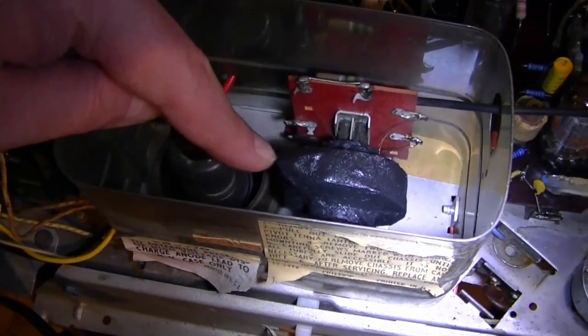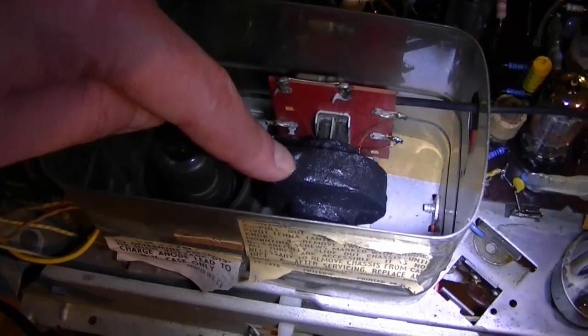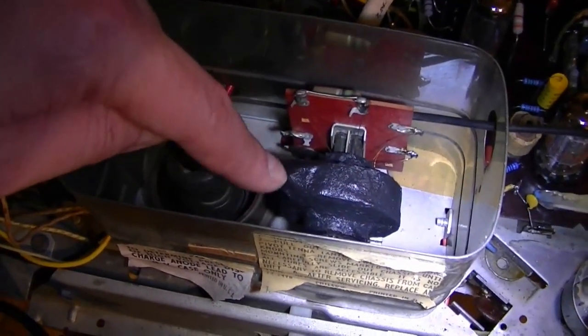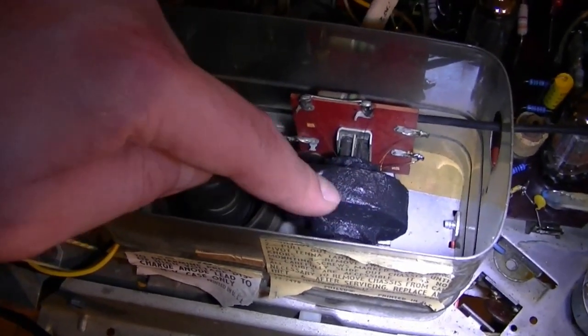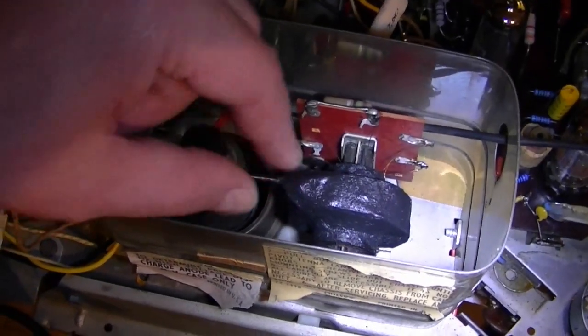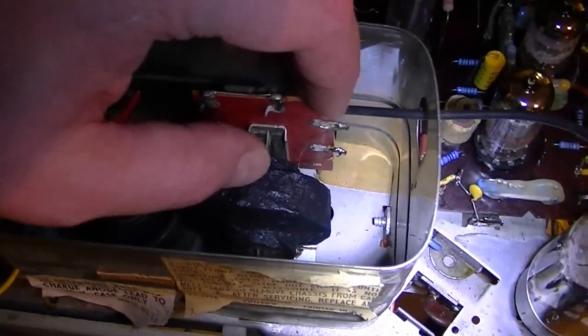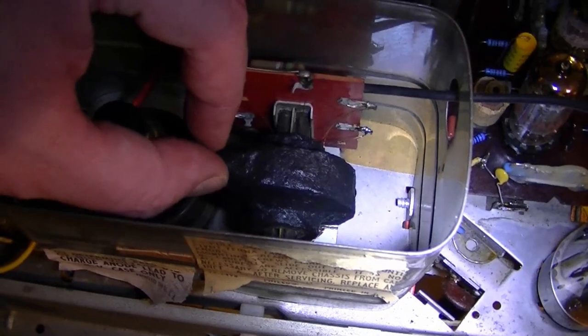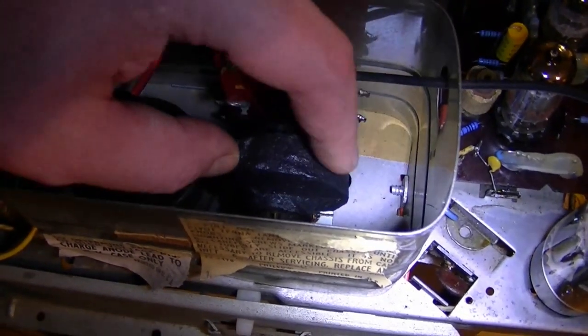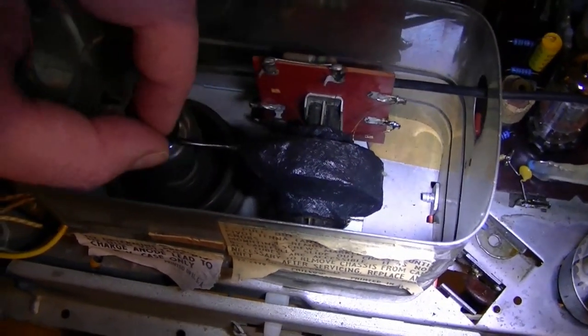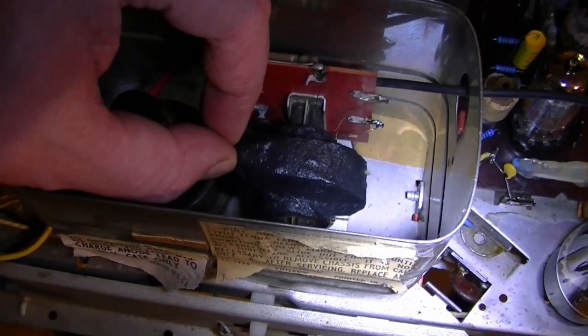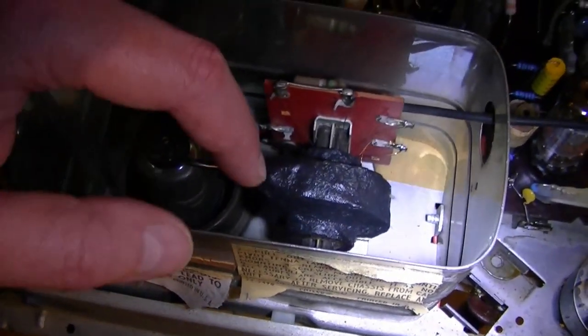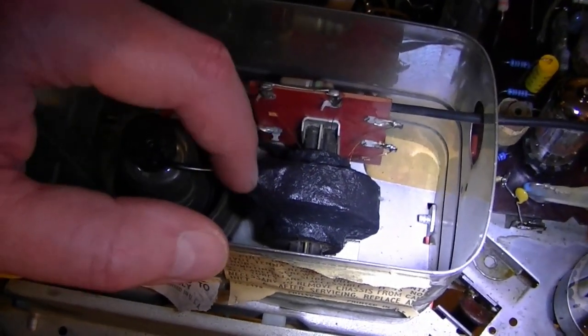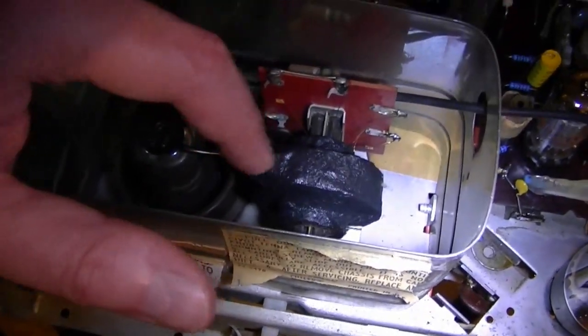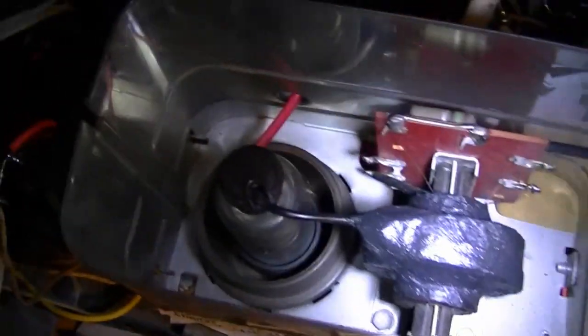This wire isn't going straight into that high voltage winding - there's a layer of insulation wrapped around the outside, and a little piece of board material with an anchor point. The fine wire attaches to that point, and this wire comes in and solders onto it. So if this breaks off, you can carefully chip away at that coating to get to the lug and reattach the wire, hopefully.